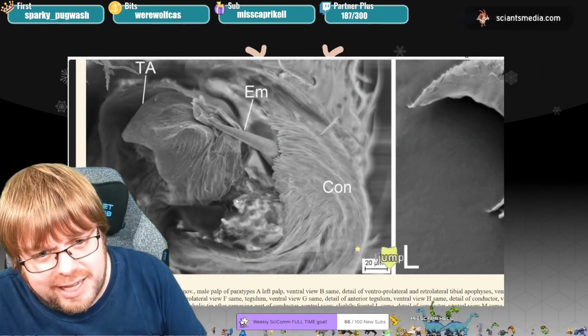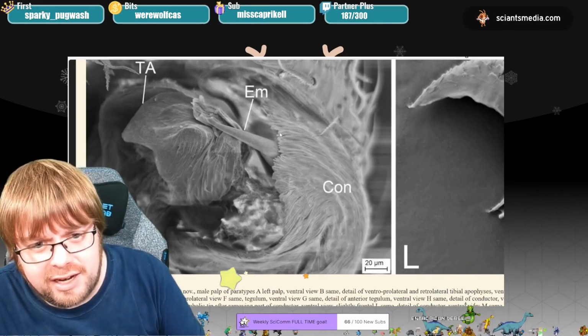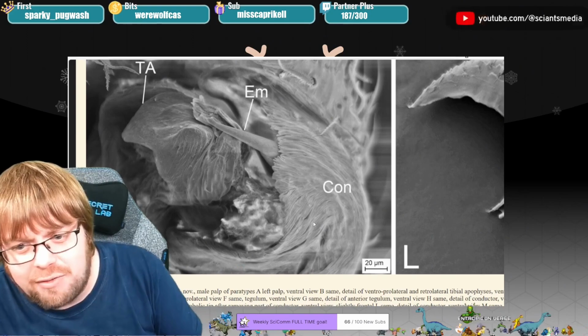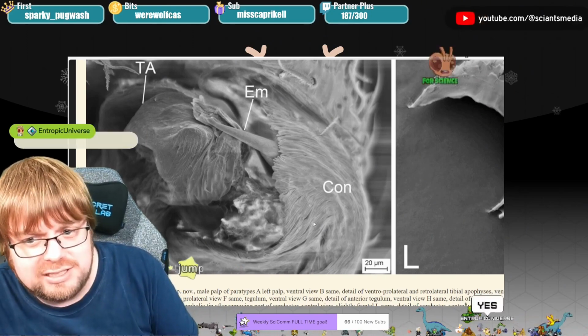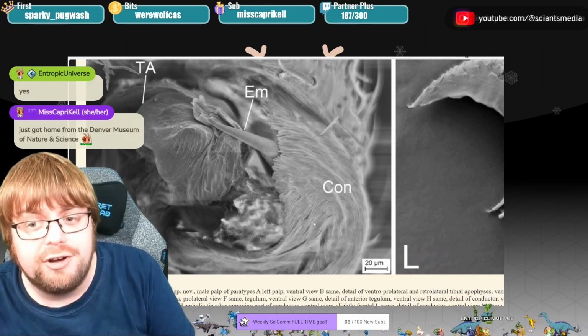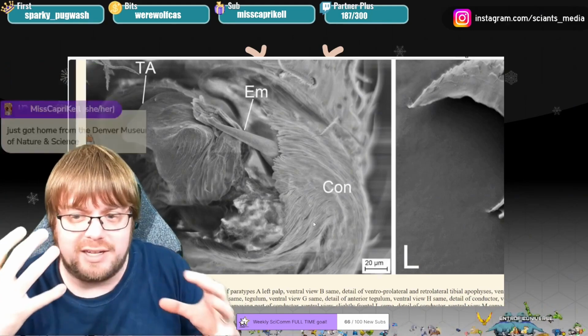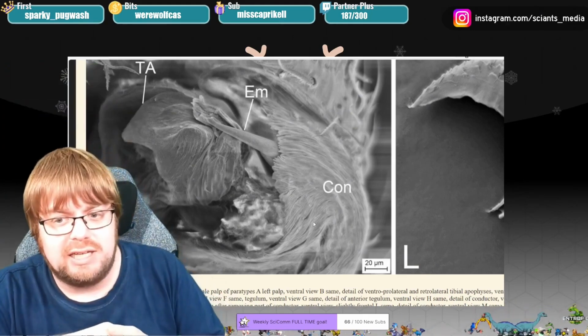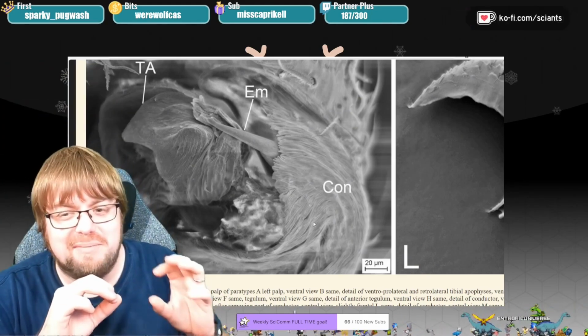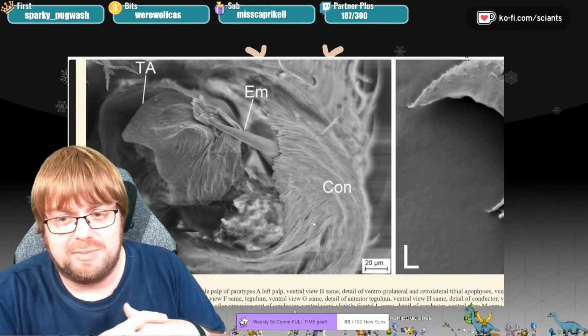Do you see, Entropic, how here it's much whiter than it is on the rest of the specimen? It's not really distracting here, but it is much whiter, right? That is called charging, where it's undercoated, and you can imagine if the whole specimen is that white in color, you're not going to get any detailing. So a lot of times it's that process of coat it a little bit and then put it in the microscope and see what it looks like.